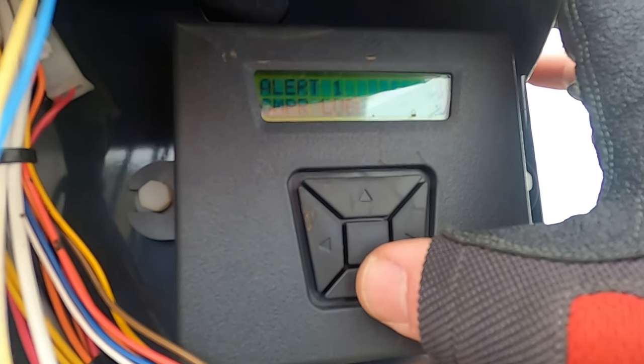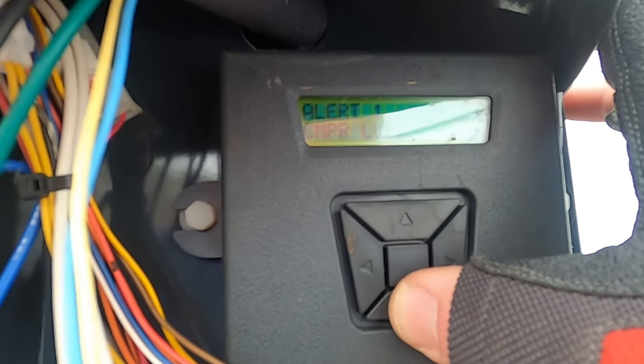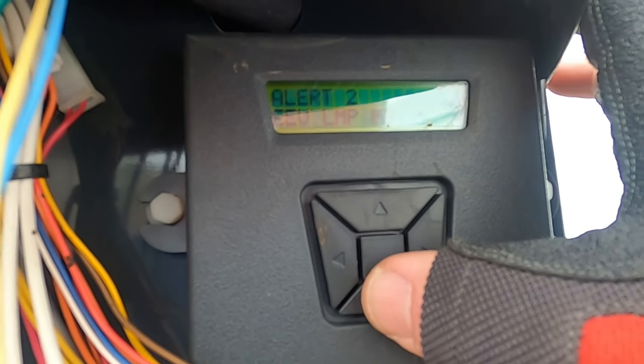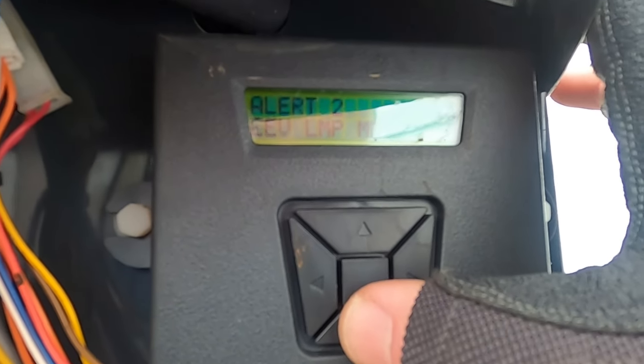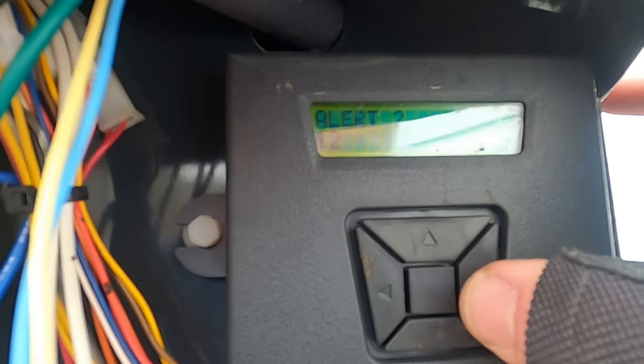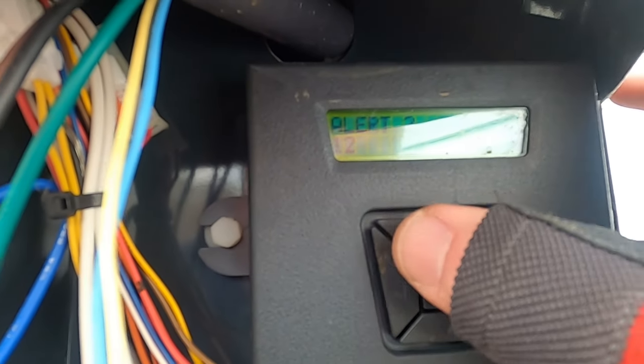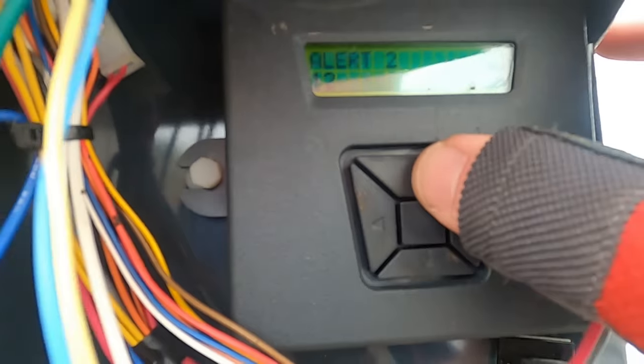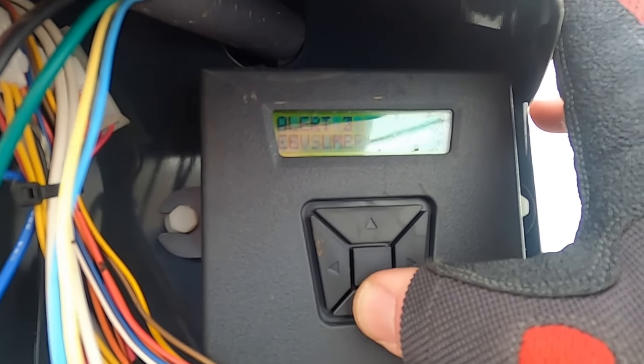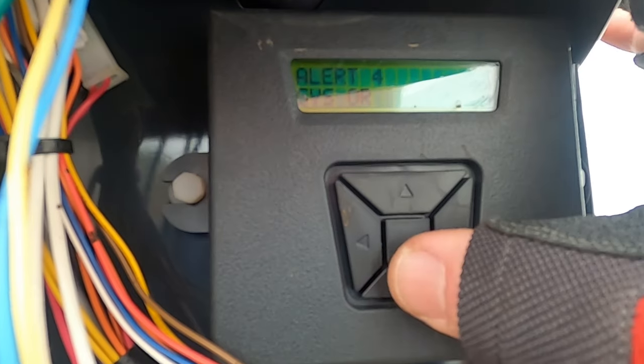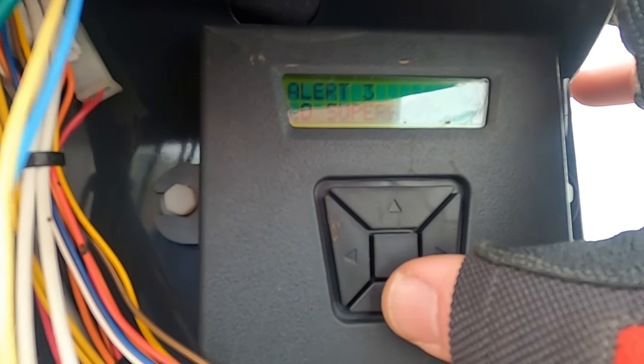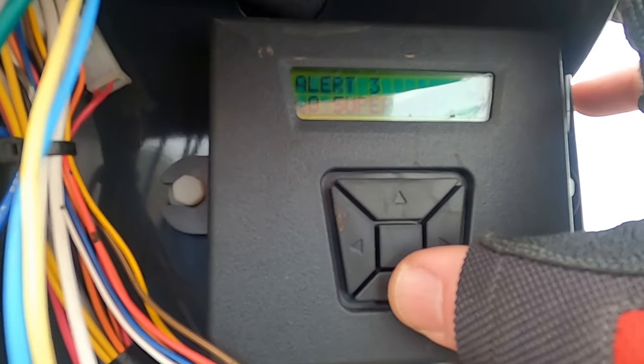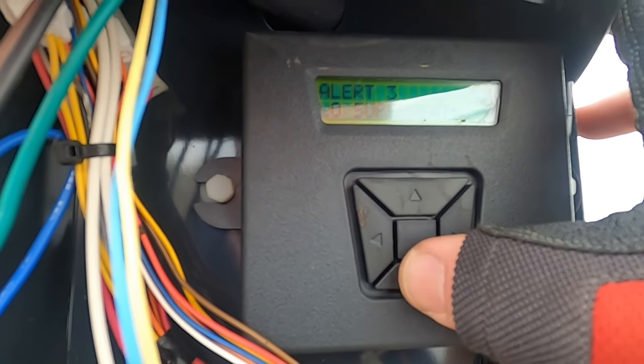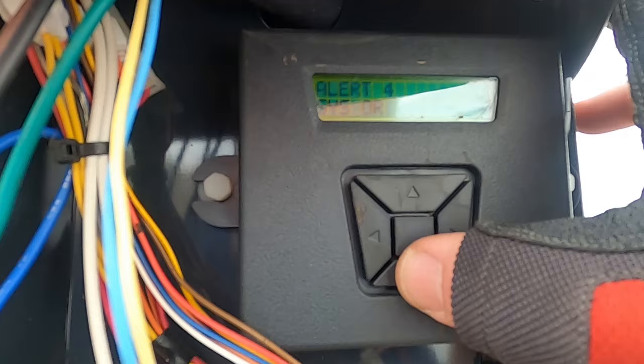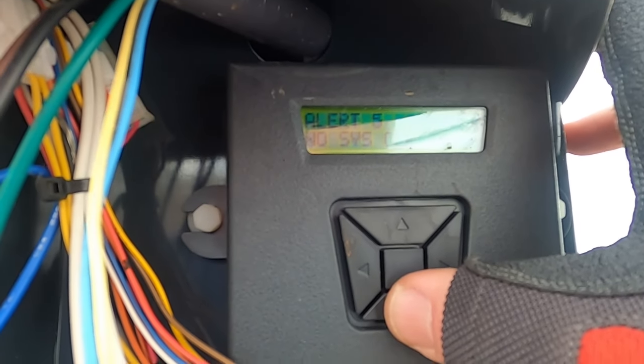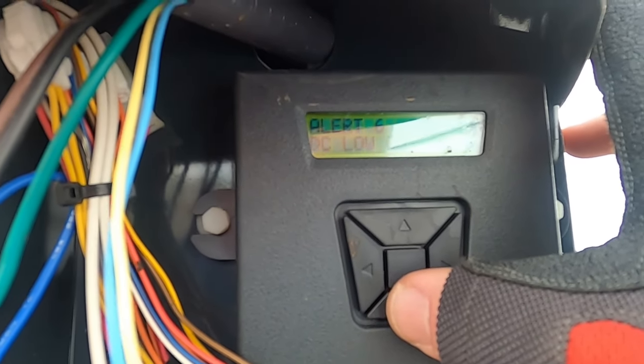We'll go down one. Compressor lube, which is normal. EEV, it was in limp mode. Alert 2. So anyway, that's what the 12 up there means. I don't know how well you can see that, but there's one low superheat fault. That might have been from going through maybe a defrost cycle or something on a real cold night. I don't know. We'll run it and check it. There's system oil return, and that's that clock one.